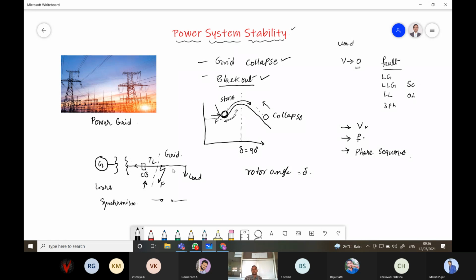Before the fault affects the generator or any power system, we need to clear the fault. That angle is called the critical clearing angle. We will study these things in coming classes. What is the critical clearing angle, and the time within which the fault must be cleared is called the critical clearing time. These terms are referred to from the stability point of view: critical clearing time and critical clearing angle. Before that time, we need to restore the system and clear the fault. Then the power system will be healthy.